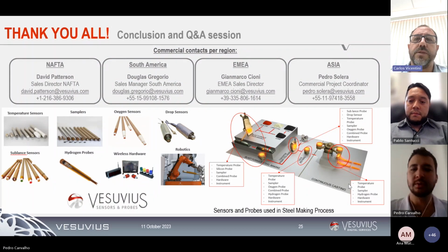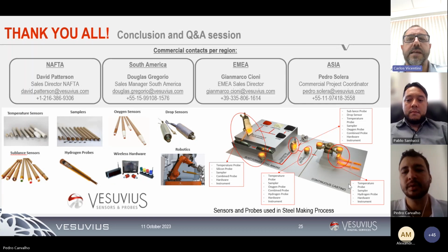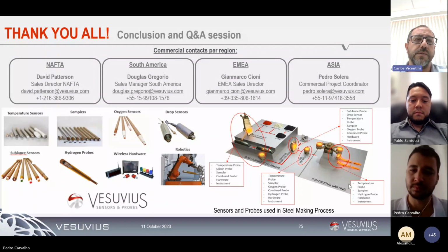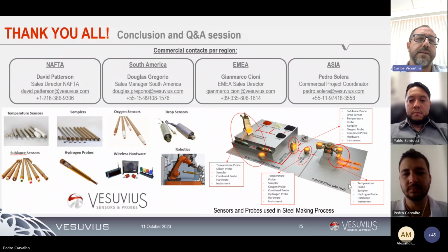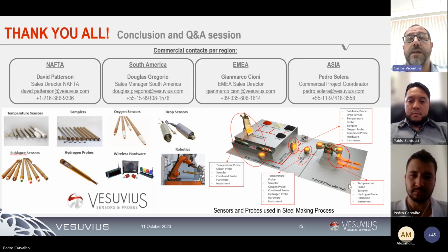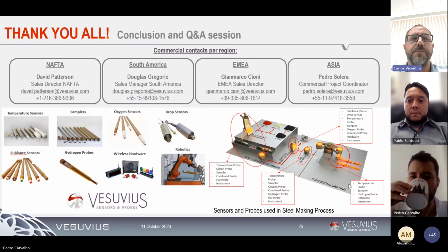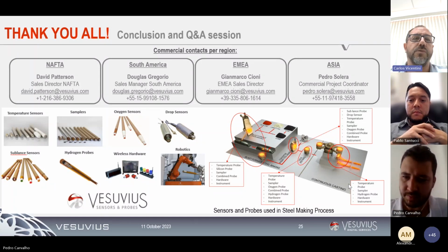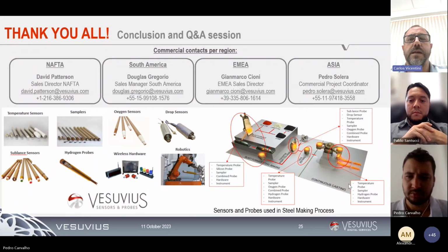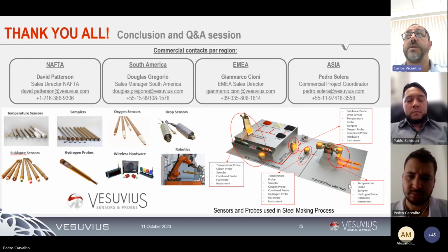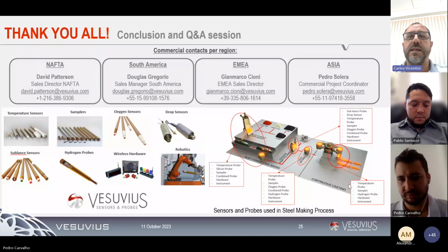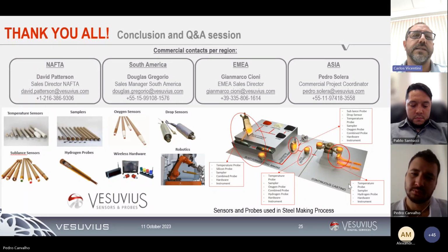Yeah, but it's very important to understand that when you're talking about customization, as according to Pablo's explanation, it is in terms of the basic function of our solution, when you're talking about, for example, the equipment, the lance, or the probes. But we also help a lot of customers change, for example, from manual immersion to automatic immersion. Of course, we can help the customer customize this application, because to take this measurement, the time is very long, within 35 seconds to 65 seconds.